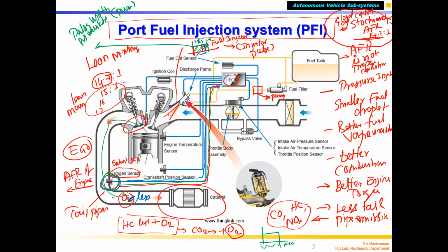Correct. Fuel quantity is more than the oxygen available. So all the oxygen molecules are already used up by this. Excess CO, and HC is coming, unburned fuel, correct? That means no oxygen is available. There's a separate sensor, the HC sensor, but the oxygen sensor doesn't detect that. It sees that there's no oxygen.